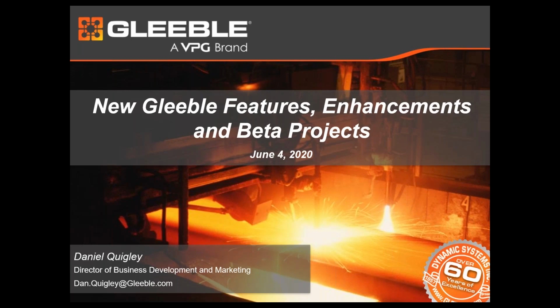There's a question here about the temperature range for the induction heater. The temperature range for the induction heater would be the same as the temperature range for the standard Gleeble. We peg that temperature range at 1,700 degrees Celsius, typically because of the heat load in the tank. That is what we can definitely guarantee the Gleeble will do for normal sample sizes, although we routinely have customers that exceed that with smaller samples that won't put too much heat load into the tank. So we can do that as well with the induction heater.